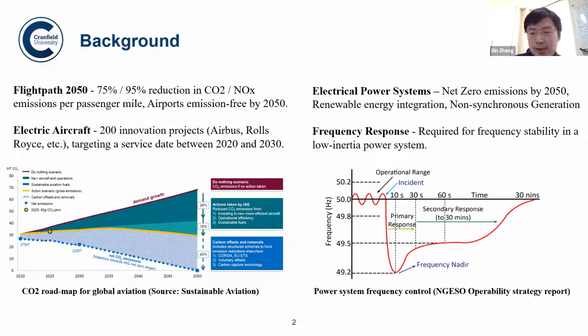One aspect is frequency, especially frequency response. A lot of additional frequency response is required to stabilize grid frequency in a future low-inertia power system. This figure shows a typical power system frequency control from a National Grid ESO operability strategy report. Frequency is stabilized around 50 Hertz, and when a sudden incident happens, frequency could fall very quickly to a very low point beyond the operational limit. Then primary frequency response and secondary frequency response are needed to arrest the frequency from falling and restore it back to the operational limit.